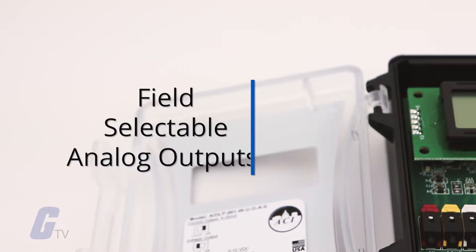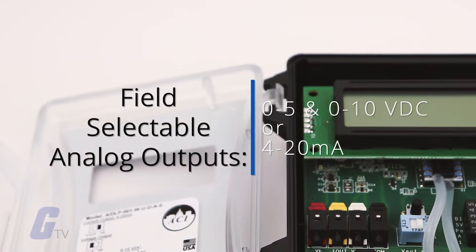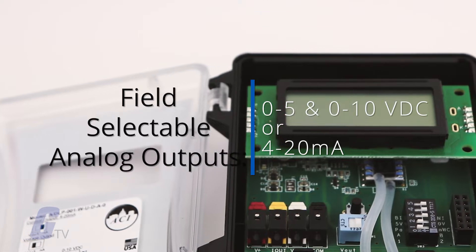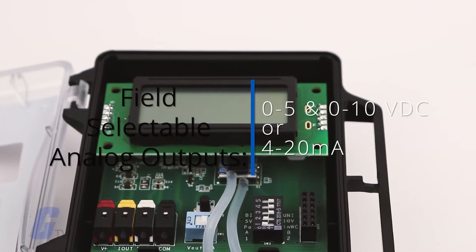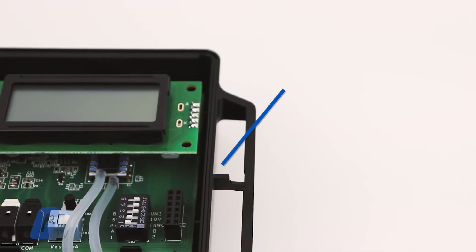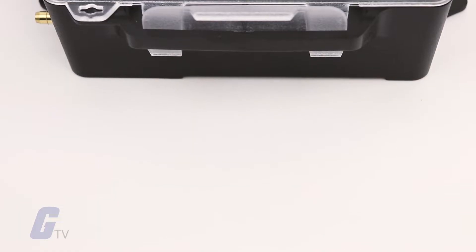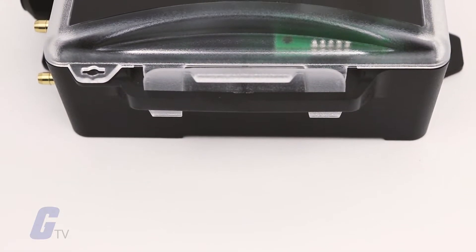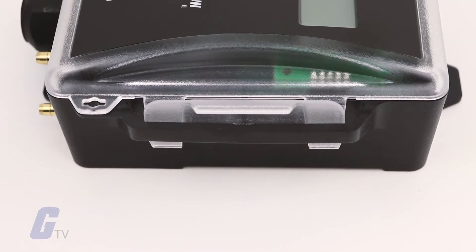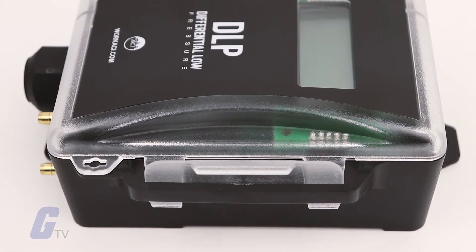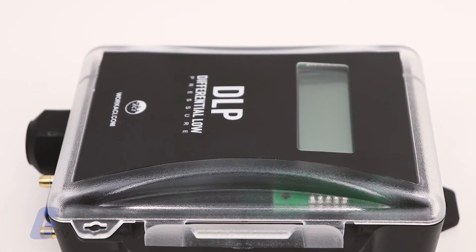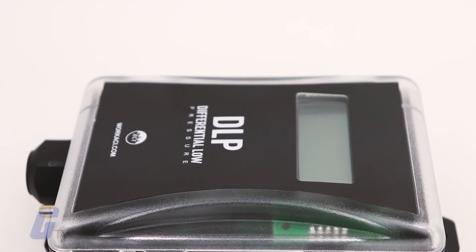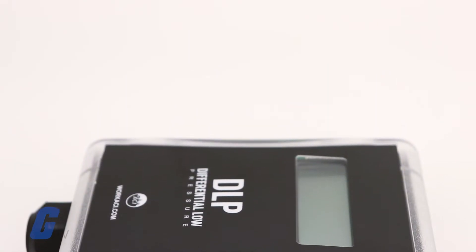Field selectable analog outputs include 0 to 5 and 0 to 10 volts DC or 4 to 20 milliamps which correlate to a unidirectional or bidirectional pressure range from 0 to 0.1 inch up to 0 to 40 inches of water column depending on your model selection.